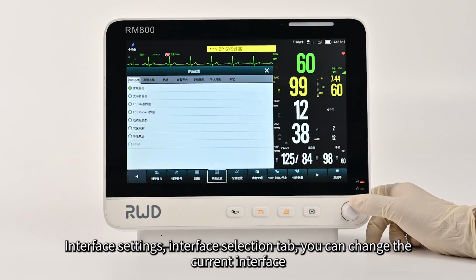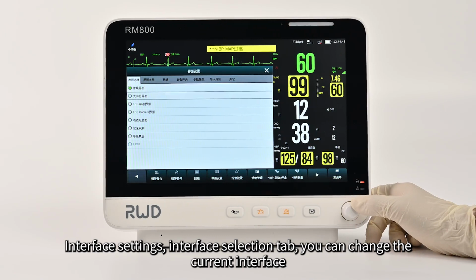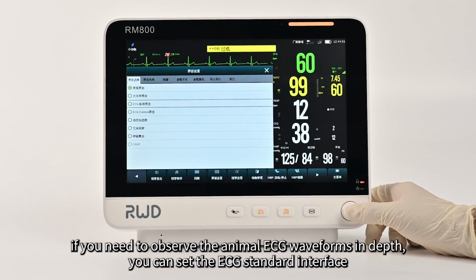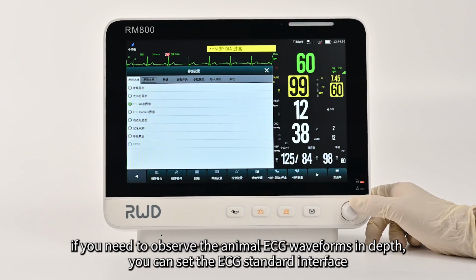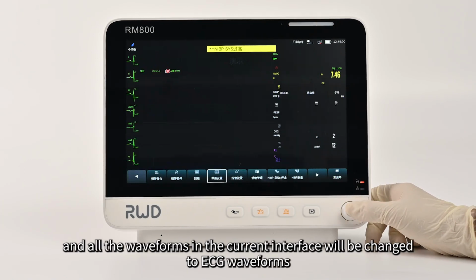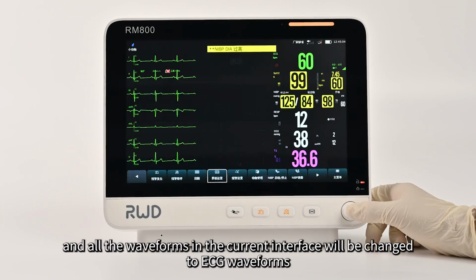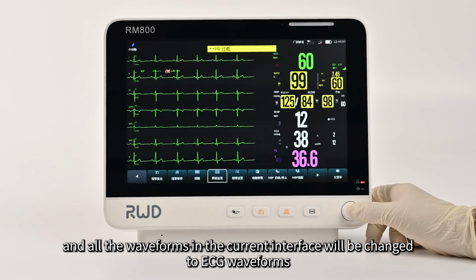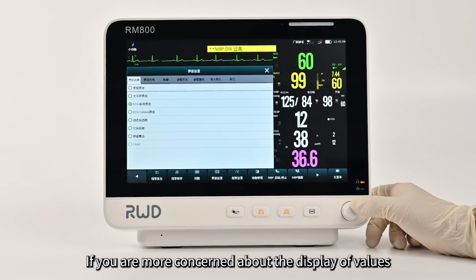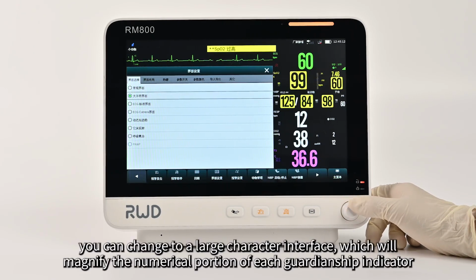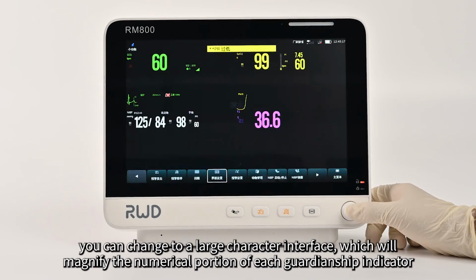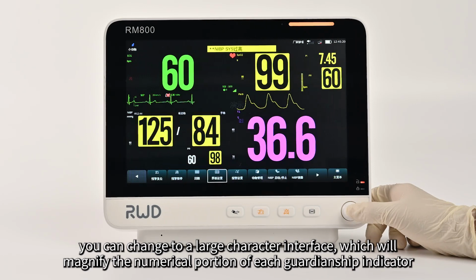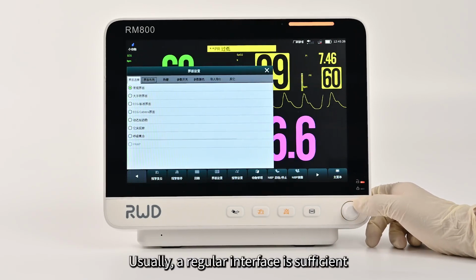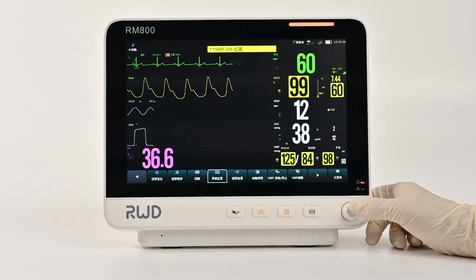Interface Settings, Interface Selection tab. You can change the current interface. If you need to observe the animal ECG waveforms in depth, you can set the ECG standard interface, and all the waveforms in the current interface will be changed to ECG waveforms. If you are more concerned about the display of values, you can change to a large character interface, which will magnify the numerical portion of each monitoring indicator. Usually, a regular interface is sufficient.